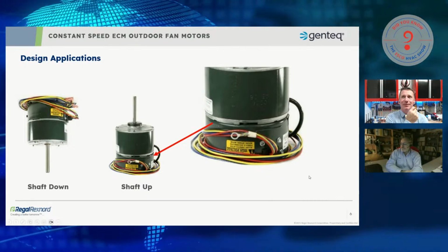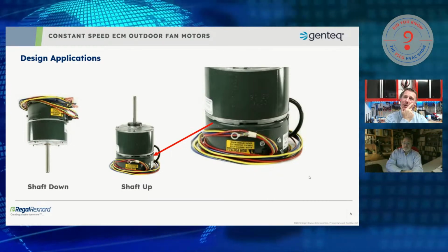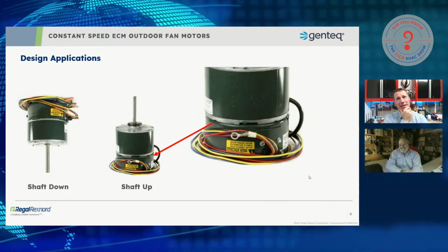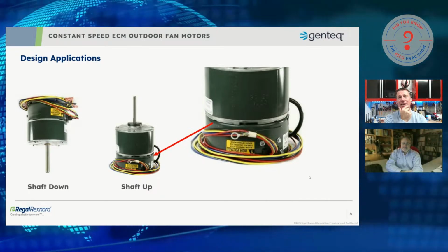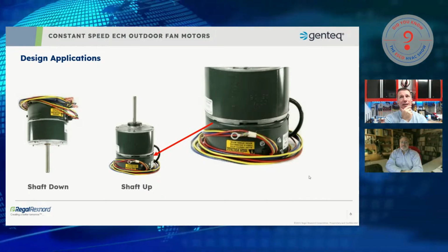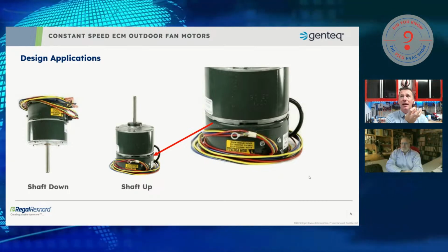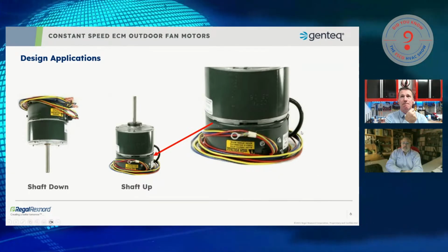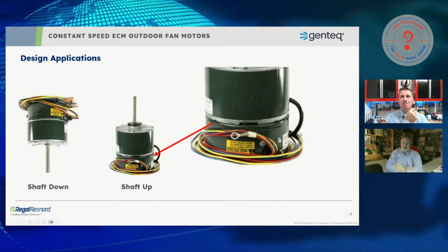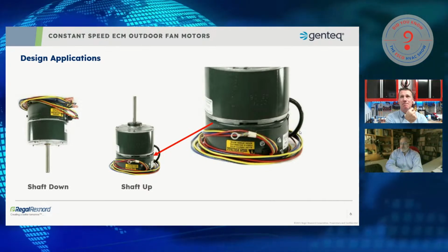And it's very unlikely that water is going to collect in there and pool back or wick back up to the electronic control. And I've seen this design, and every time I look at it, I go, okay, let me look here. What am I seeing? And I kind of recognize that our control was configured different, and now it makes complete sense. So if you see that little jug handle, that usually means you've got a shaft up motor and the control was flipped over on purpose.